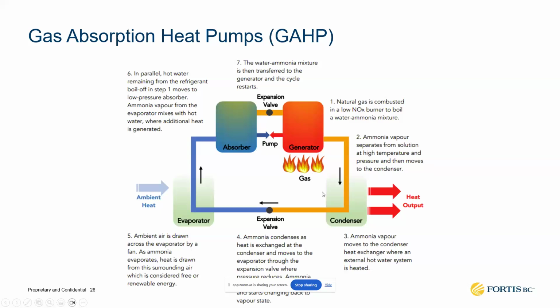In other words, think of your absorber, your pump, and your gas generator as doing the same function as your compressor. This is the main difference: it uses a little pump and a gas burner to do the same work as the electrically driven compressor would. And this is a very, very high level overview of how a gas absorption heat pump works.